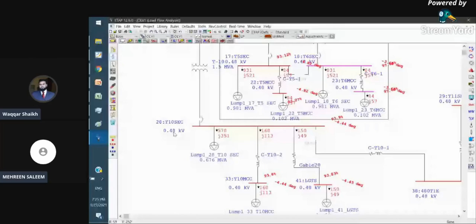We have 93.8% voltage here, 93.83 here, and some voltage levels shown here, 93.9, which is below the required limit. These three buses, bus 28T10 sec, 33T10 MCC, and 41 lights, are being powered from the nearest transformer, this 1.5 MVA transformer. So I am just changing the tap of the transformer. I am lowering the tap by minus 2.5% and running the simulation now. You will find that the voltage has recovered to 96.36, 96.45, 96.39. So now we are in the safe range of the voltage limits as per the standard requirement.